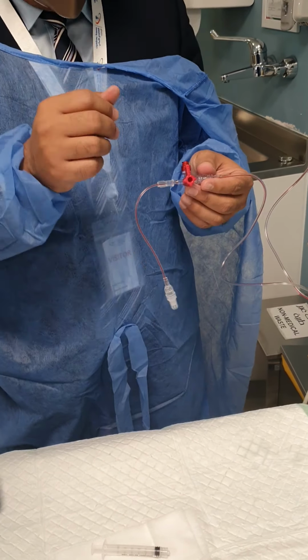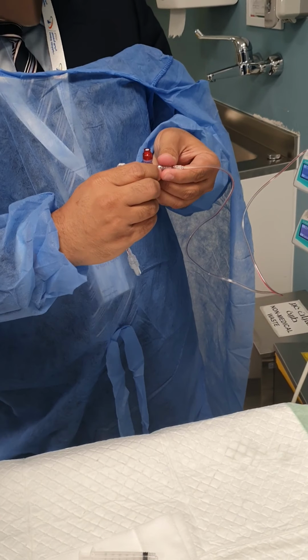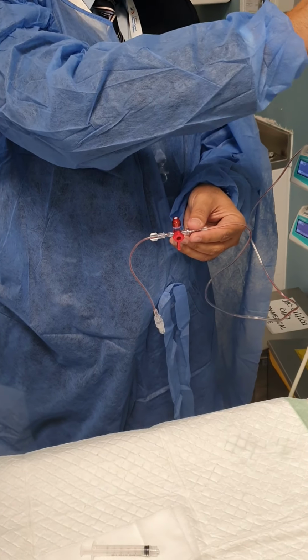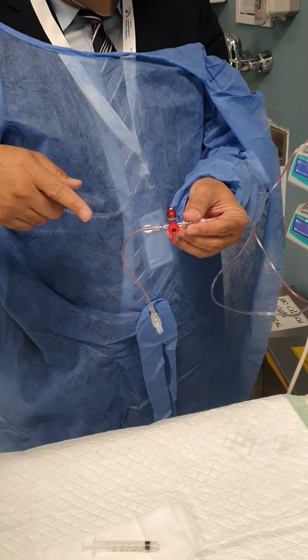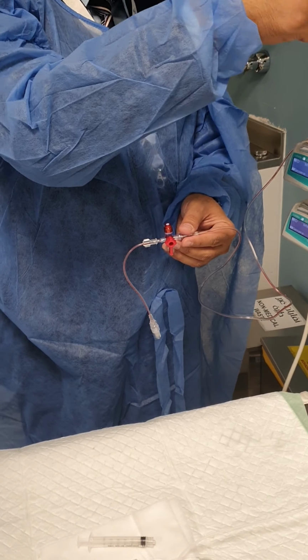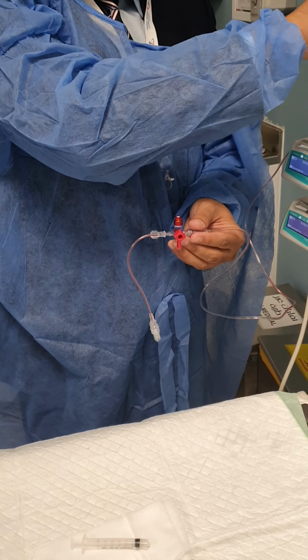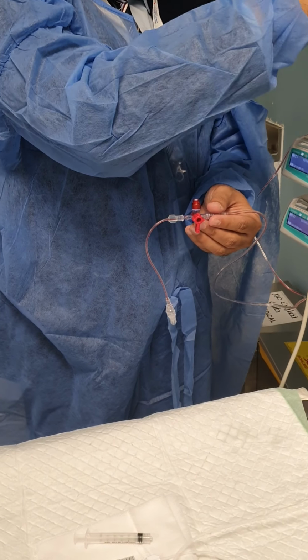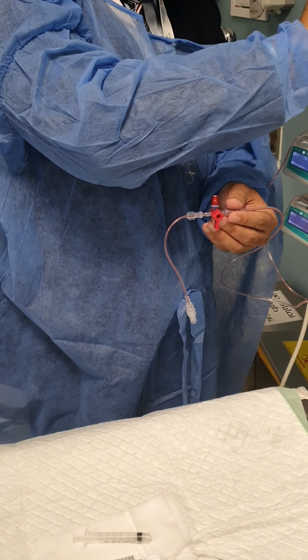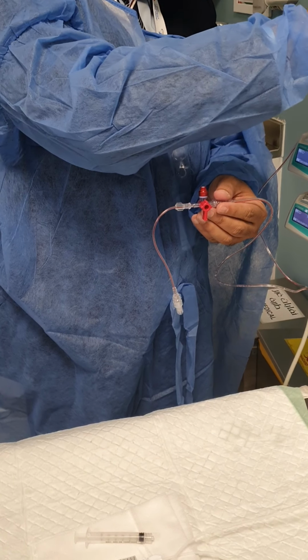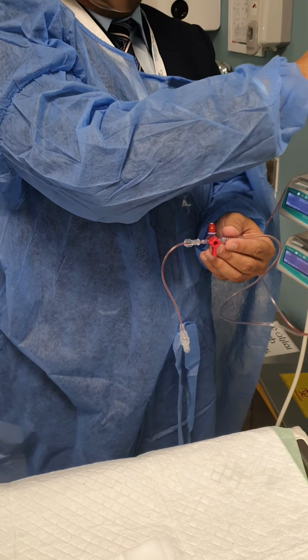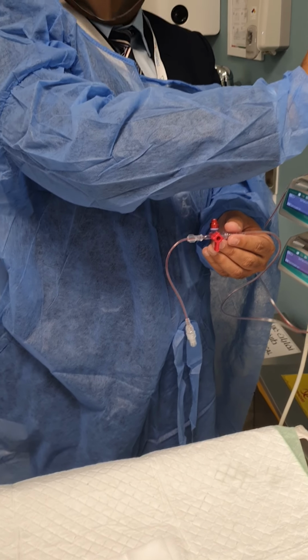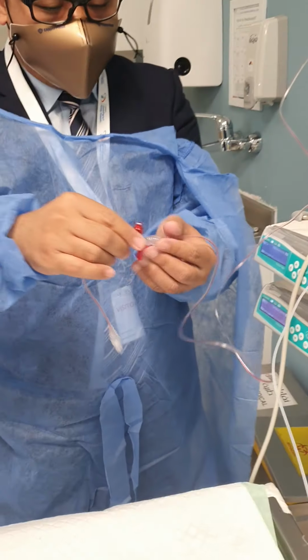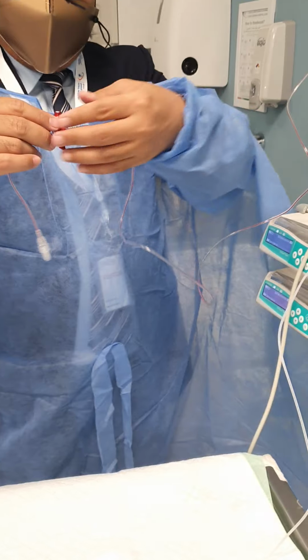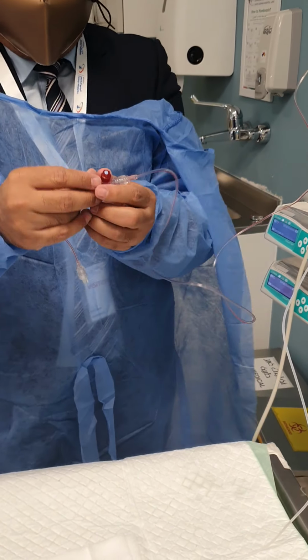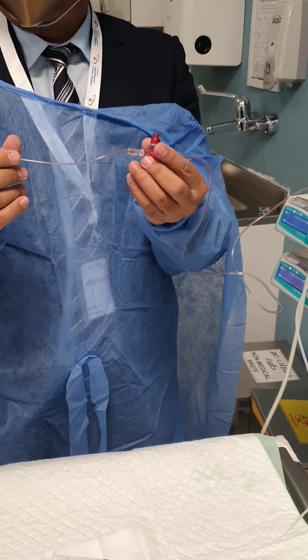The short procedure is to put it in flush position. This is a reservoir, so negative pressure would go through this line. For neonates, just a small turn would do, because for adults you have to turn at least, this is 3 cc. So we don't need that much. One turn or whatever you see is possible. Blood with saline would pass through this part. We close it. So we have access now to pure ABG.